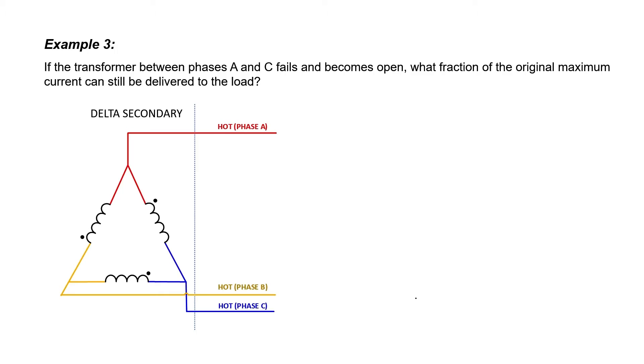with a delta connected transformer, it still works if one of the three transformers in the bank fails. That's what we're going to look at here in this particular example. Let's assume that the transformer here between phases A and C fails and becomes open.